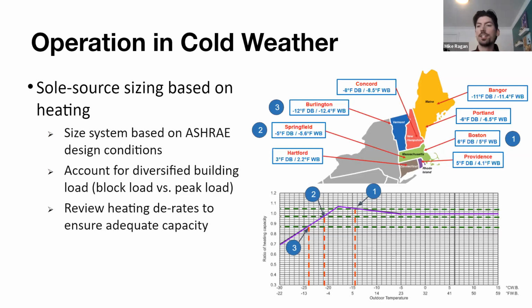So in our respective design softwares, we're going to be running the built-in simulation software that determines the output at each fan coil. If we find that the derate that our system is seeing is too much for that given climate, we're going to upsize our outdoor unit. If we're not going to be able to output as the sole source of heat on design day conditions, we're going to want to make sure our outdoor unit has more capacity. So effectively, when you're sizing a sole source of heating VRF system, you're going to be taking into account ASHRAE design conditions. You want to make sure that on design day conditions, you have enough heat output from your system to comfortably heat the space.